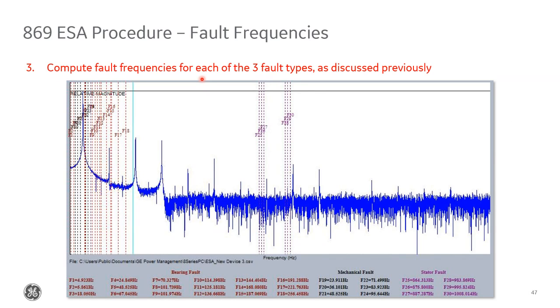So continuing on, in step 3, after we take a look at the Fourier transform, we calculate the fault frequencies for each of the 3 fault types using the formulas that we looked at a little bit ago. This is a snapshot of the ESA FFT taken using the 8 series setup software. You can see all the flagged fault frequencies. Again, we show you this version of the FFT regardless of the relay firmware for visual simplicity. This is an actual screenshot from one of our customer installations running older firmware. So you can see double the number of fault frequencies flagged than you would if you had the latest version, but all the same, the bearing frequencies are marked in red.